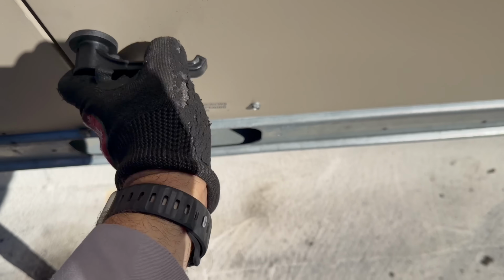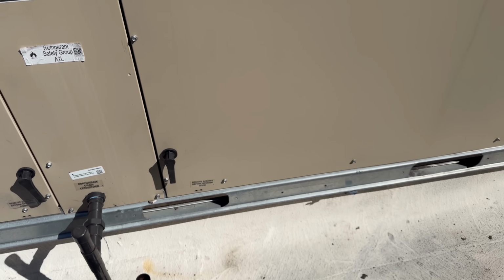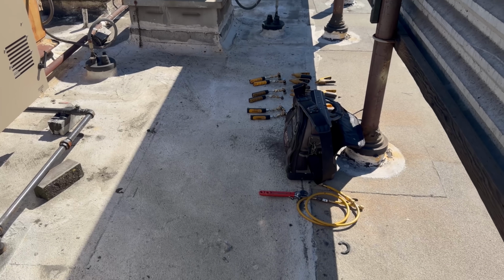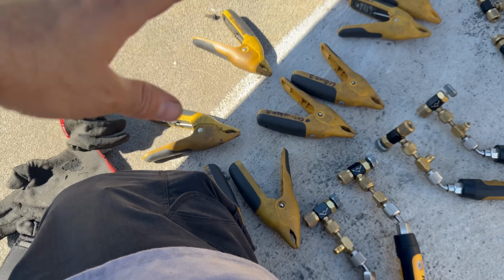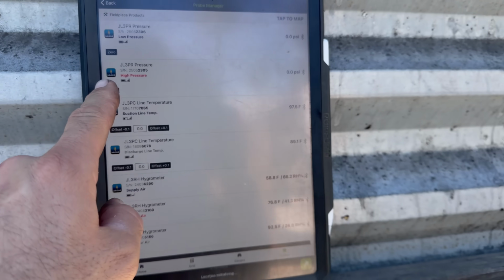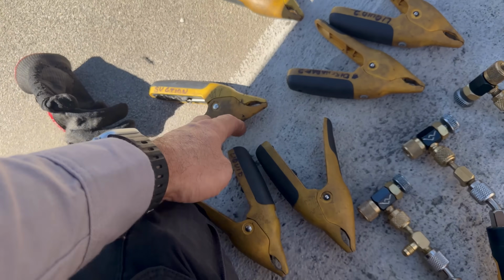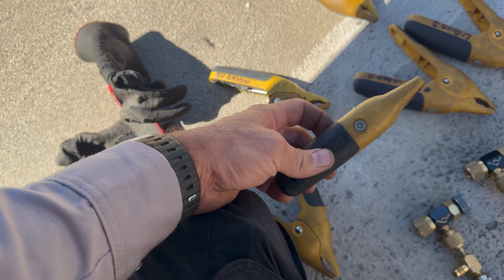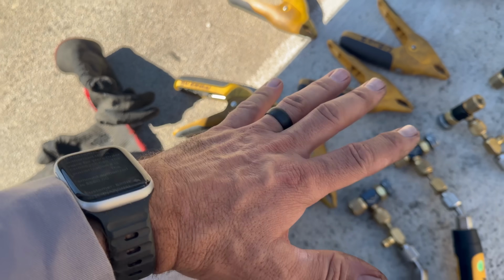So we're moving air. We're going to close all these panels. All that information needs to be known before we probe up, because remember, airflow before charge. Got to be really thorough. Make sure you're checking each one as you turn it on to make sure the pressure probes are zeroed out and the temperature clamps are matching. Especially when you have this many, it's easy to get them confused. Now I write on them, but still it's a good thing to watch each one get turned on and make sure they're all zeroed out when you start them up.